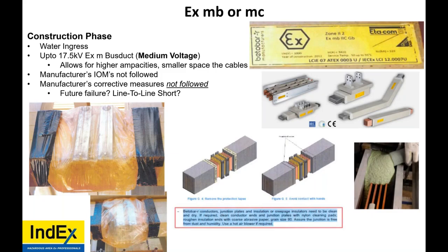What happened? The manufacturer's IOMs, installation, operation, and maintenance manuals, were not followed. So what were the manufacturer's recommendations? They said that it shall be clean and dry. If required, clean the conductor ends, use a roughening pad or abrasive paper to roughen them up, and they shall be free from dust and humidity. Use a hot air blower. None of that was done on this connection.